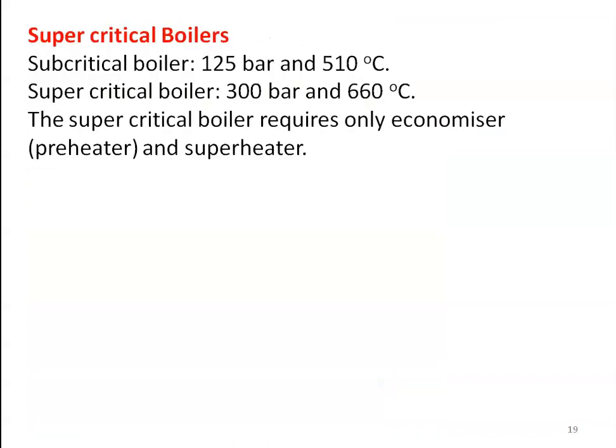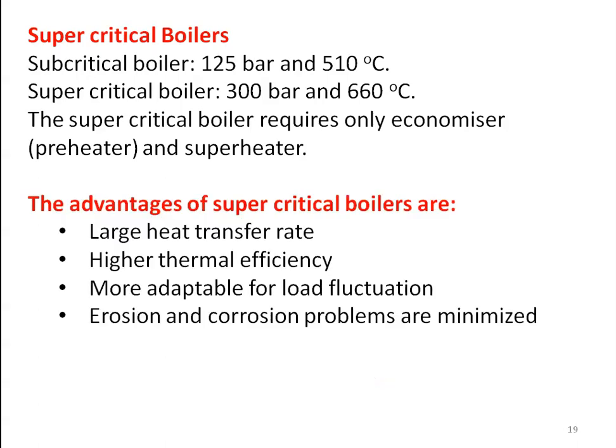Depending on the boiler pressure, we can classify boilers into subcritical and supercritical. For a subcritical boiler, the pressure is around 125 bar and temperature is 510 degrees Celsius. For a supercritical boiler, the pressure is above 300 bar and temperature is 660 degrees Celsius. The supercritical boiler requires only an economizer and the superheater — sometimes there is no evaporator; we have a number of tubes through which water is heated and converted into steam. The advantages of a supercritical boiler are: large heat transfer rate, higher thermal efficiency, more adaptable for load fluctuation, and erosion and corrosion problems are minimized.